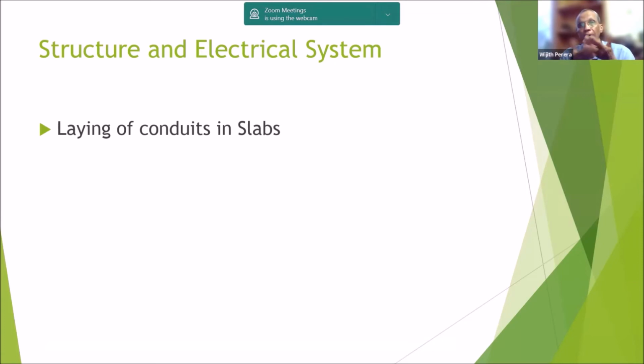But our requirement of the conduits is on the slab and towards the bottom surface of the slab because the conduits feed the area below the slab. And we have to have conduits laid and the service points, or the junction boxes as we call them, or pull boxes, have to be accessible from the opening which we create in the bottom surface of the slab. So we run into difficulties in coordinating with the reinforcements and finding space for the conduits.